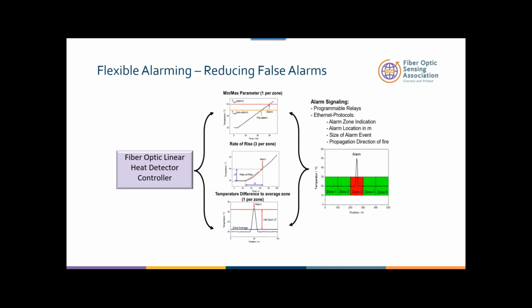The flexibility of the alarms is extremely important. In this case, we have a continuously sensing fiber optic cable. You can get temperature everywhere. The ability to know what is the maximum temperature, the rate of rise, and the ability to know what is the differential temperature within an area is the flexibility of the system.